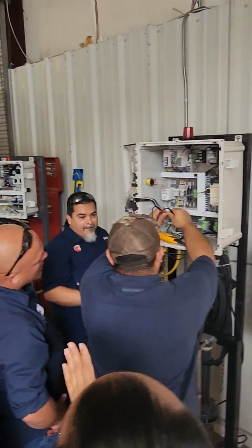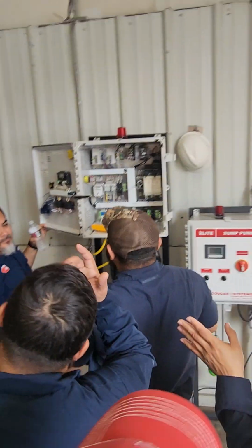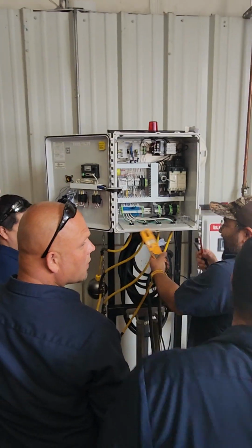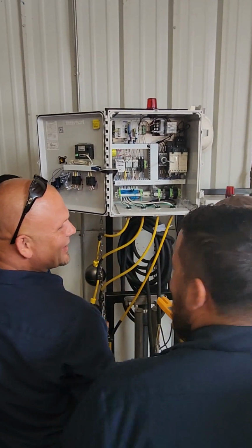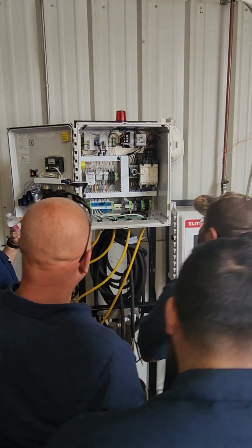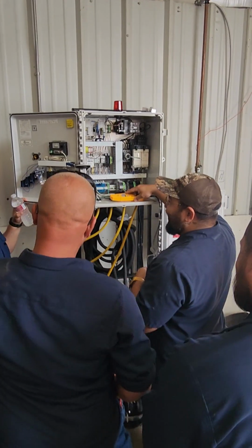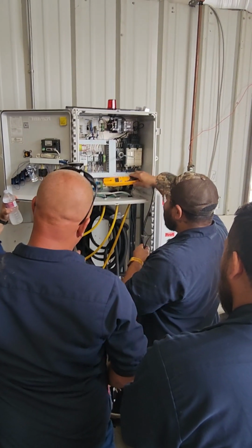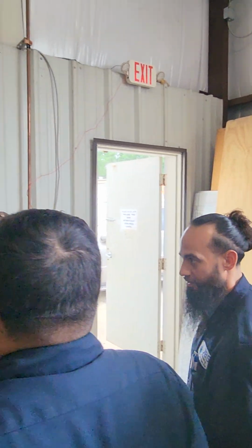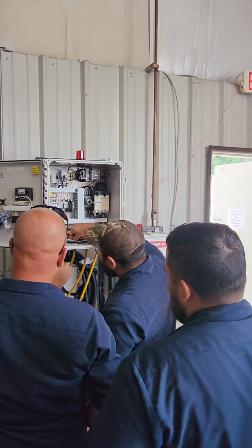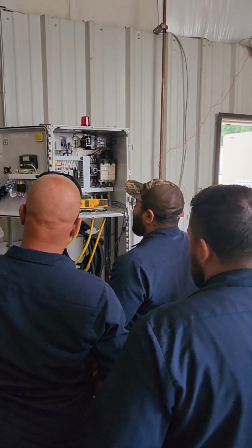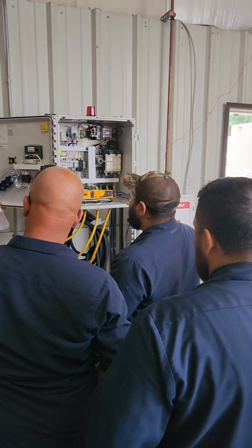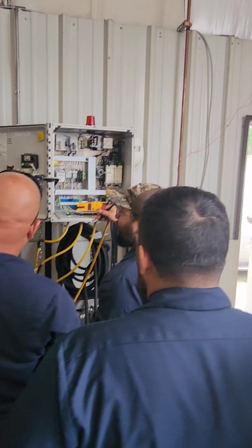Oh, so you're saying this is a 2-person job. That's what I'm saying. That's what I'm hearing. There is a time issue because we have a pit way out there. They have to go run. Like they can't hear it. Or activate it somehow and hold it and then go check it. Can you just wire nut it? On the floats, disconnect the wires and just tie them together with a wire nut. And then, depending on your hearing, if you can hear it, you can hear it.